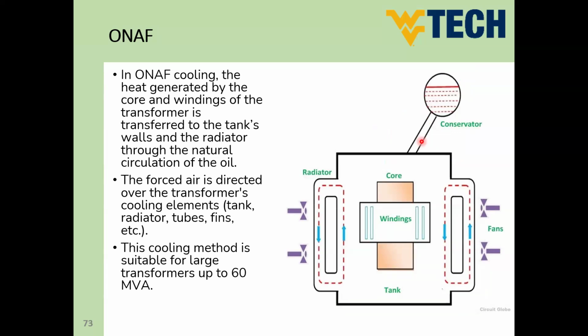We have also oil natural air forced. Oil natural means we don't have any kind of forced oil, so the oil still works with the same function. However, instead of having just a radiator in free space, we have radiators along with forced air. So we have fans to force the air to dissipate or transfer the heat from the hot oil. So this is the way, guys, in the oil natural air forced.